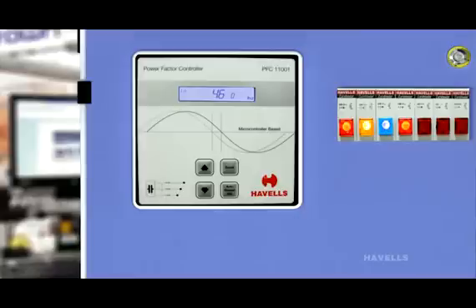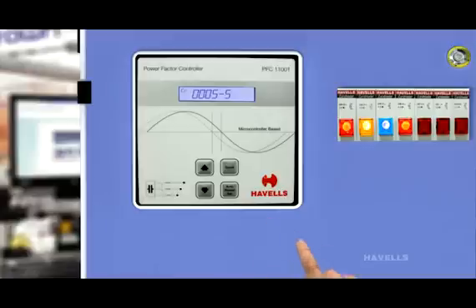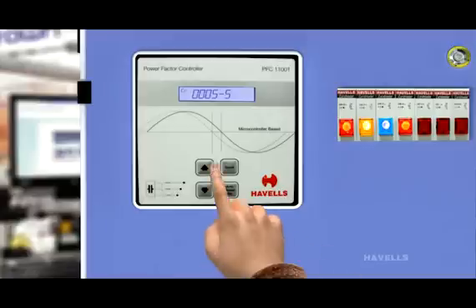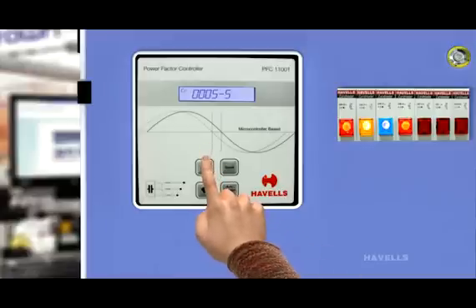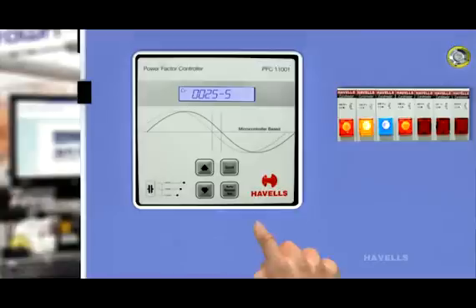Press scroll switch again. Controller shows CT ratio on LCD, which is 5 ampere. Through up and down switch, CT ratio can vary from 5 ampere to 2000 ampere.